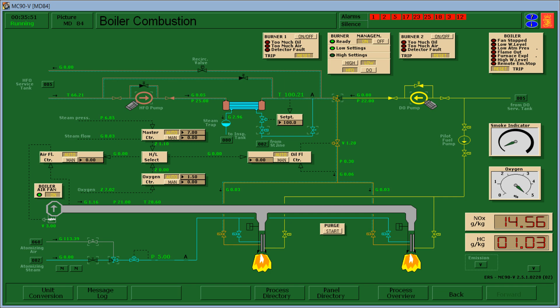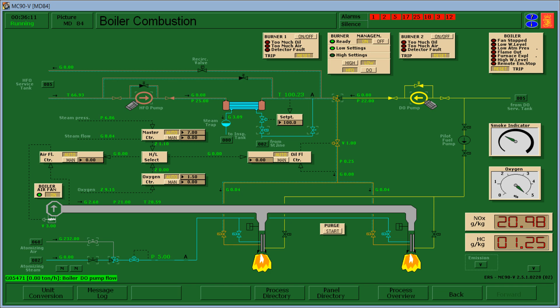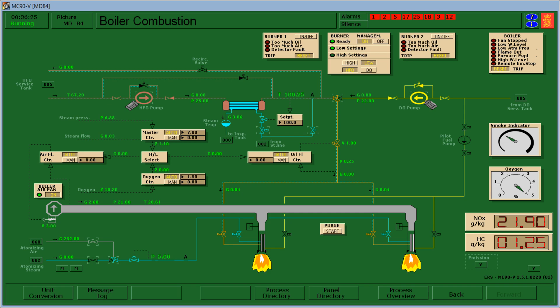Okay so we have successfully operated the boiler using heavy fuel oil. My mistake earlier is I didn't turn off the burner. So what you do is turn off the burner first, then after that you must switch this three-way valve here to HFO, and after the HFO just click the HFO switch. Then if the ready indicator is on, just click on and burner 1 and 2.